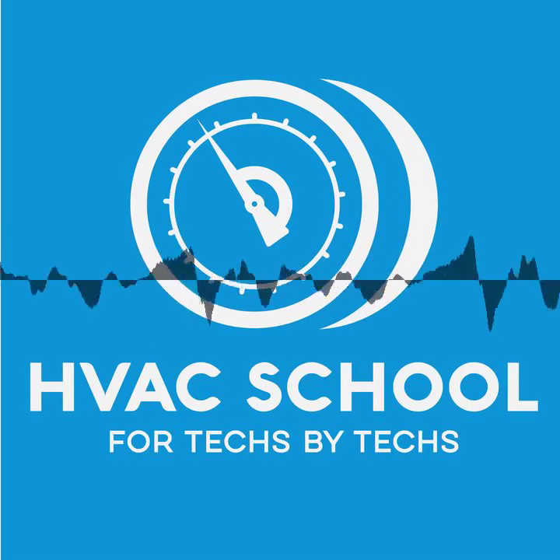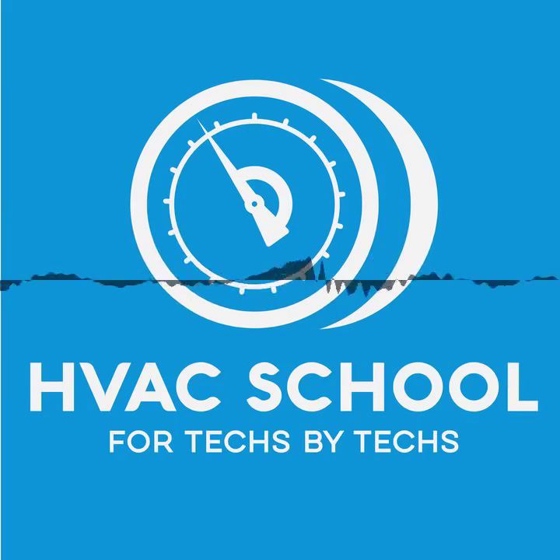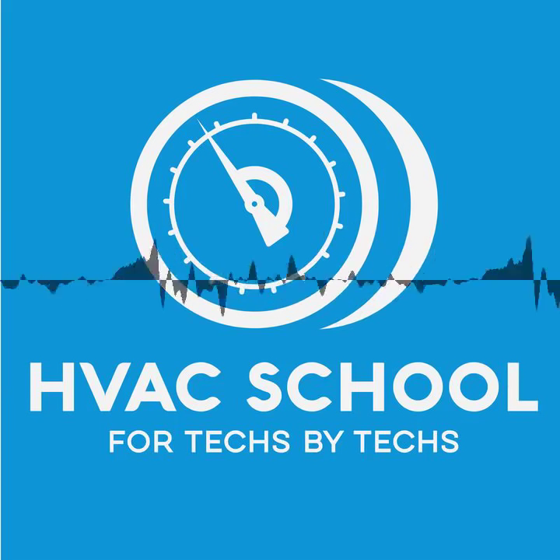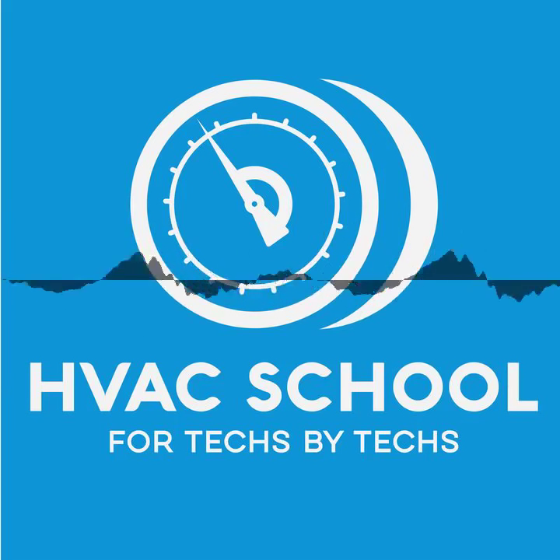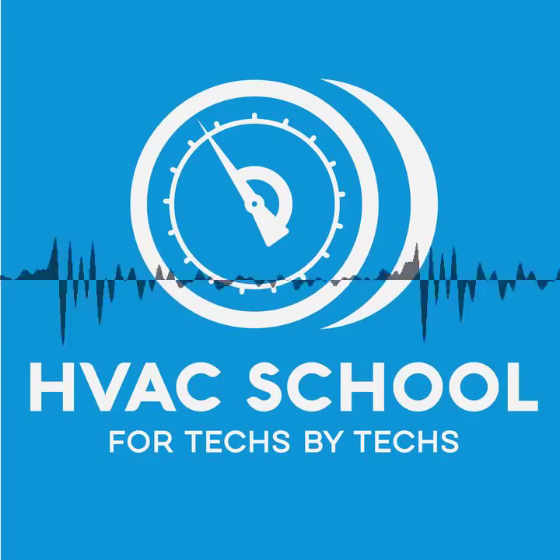Yeah. And again, a lot of what we do in refrigeration is common sense assessment. Chris talks about this all the time in his videos. He goes through and he's noticing things as he goes. Oh, okay, this is dirty. That needs to be cleaned. The seal isn't good on this door, and so on and so forth. A lot of the diagnosis is visual and common sense stuff. But it does create a challenge sometimes when you're wanting to confirm 100% that it's working properly, and you really don't want to put gauges on it unless you absolutely have to.